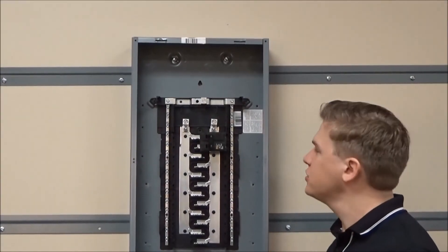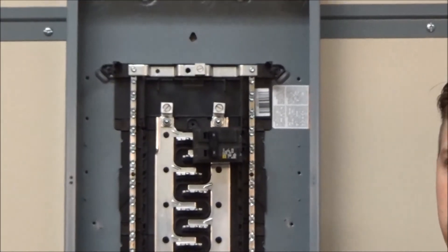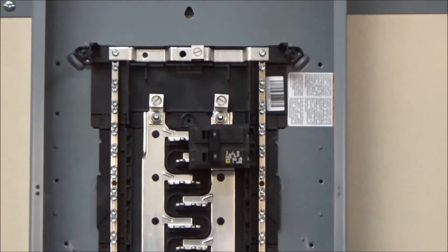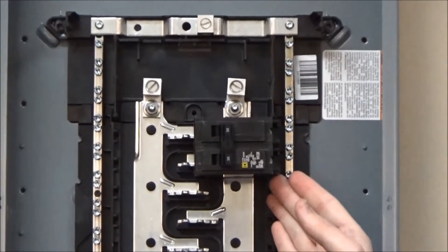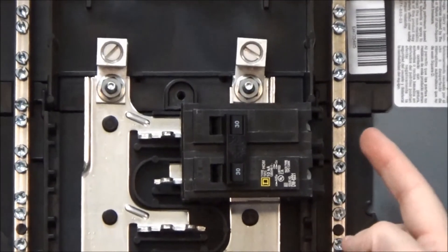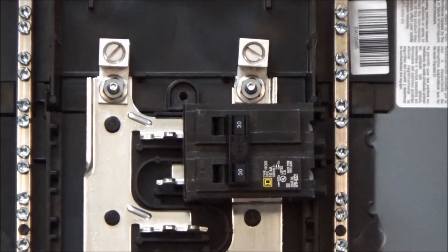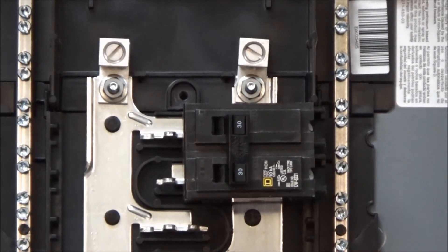Make sure that you have the correct amperage that you want to use for the main breaker and that the breaker that you'll be using is installed in positions 2 and 4 on the load center.